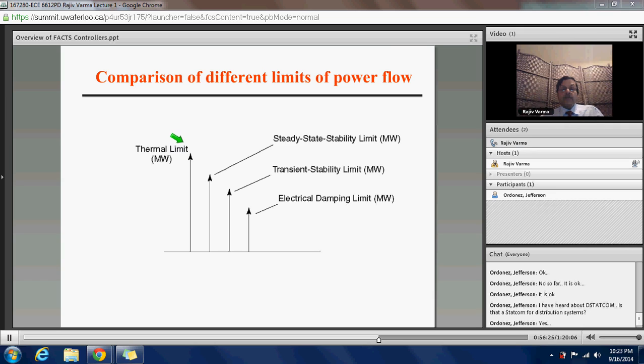Now you can have an even worse problem, the problem of electrical damping, which has been taken care of by the power system stabilizers. But there are countries, for example Sweden and Brazil, where the oscillations do get damped, so the system is stable, but it takes a lot of time for the oscillations to damp out. And that causes a limit on the amount of power that can flow on the line, because you don't want oscillating power on a transmission line for a long period of time. So what this picture tells us is that even though it appears we have a large thermal limit, meaning we can send a lot of power on the transmission line, you are constrained by the transient stability, or by the damping limit. This is becoming quite restricting.